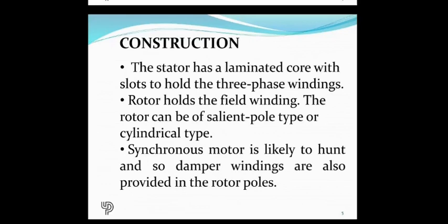There is a possibility, strong possibility, that this motor will never be able to achieve an equilibrium speed, despite the fact that in theory it should. So hunting means it is always constantly trying to hunt for the stable position. That's a practical problem, but it's manageable using things like damper windings.